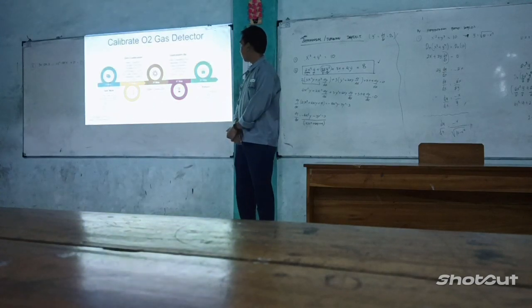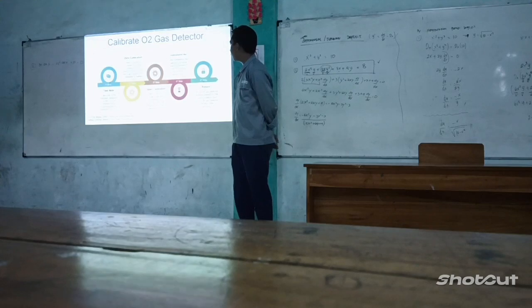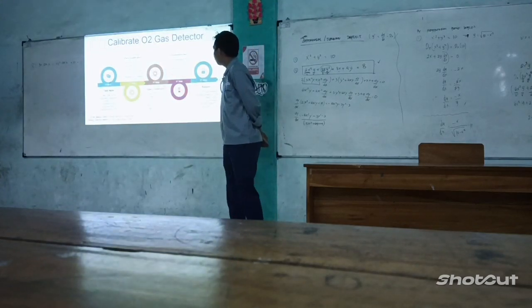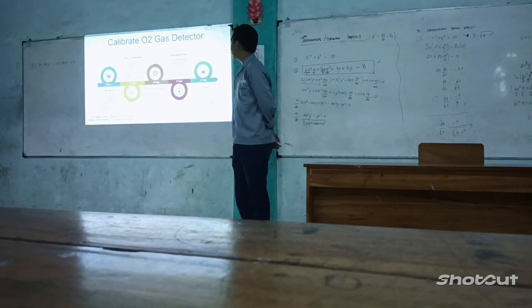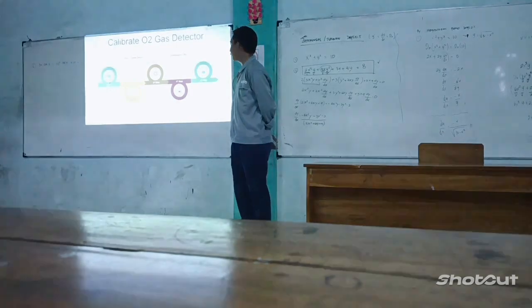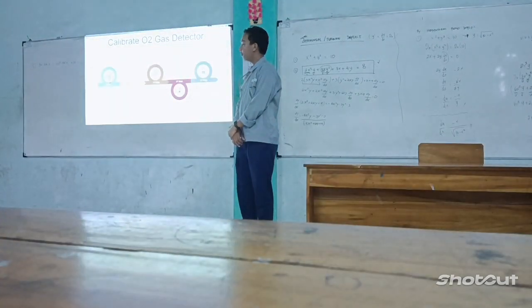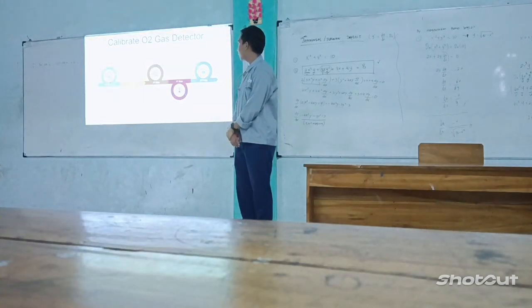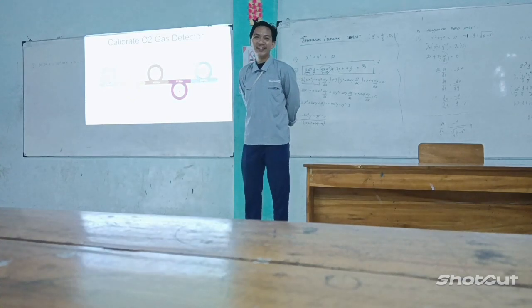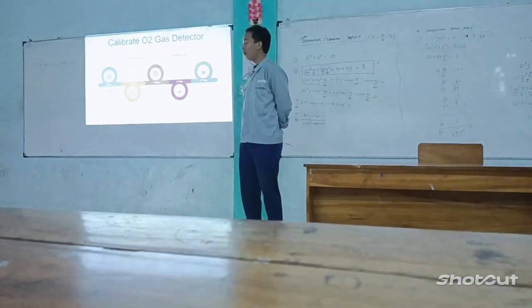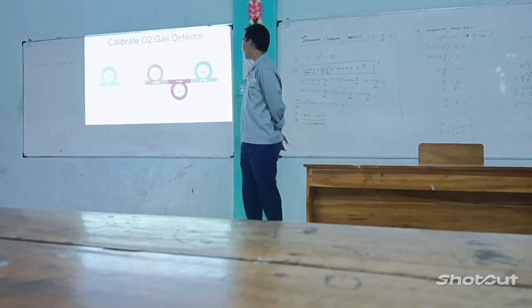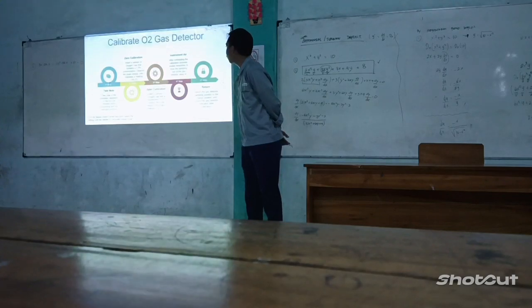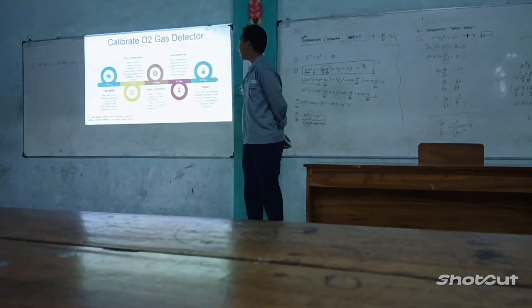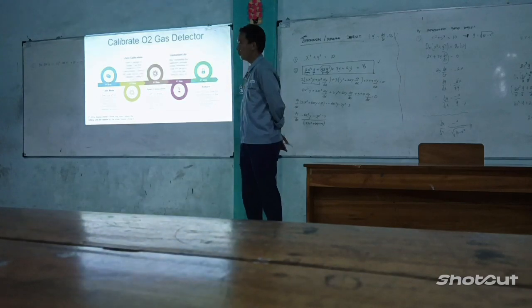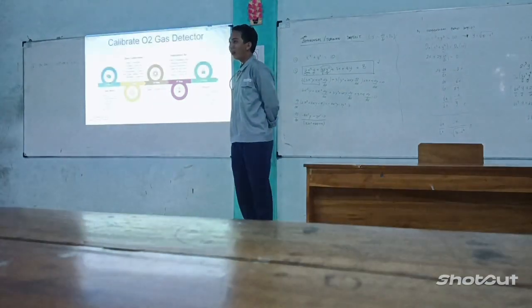This is a gas detector. The step name is zero calibration, but why do we insert 2.5%? Because my factory has a standard. The standard is appropriate for the sensor, and for any sensor, for example a pH meter, we have zero calibration at 7 and 4. Oh yeah, okay. Same like this.